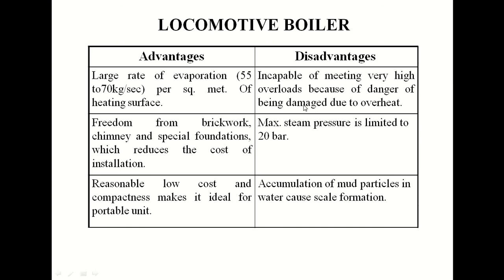And what are the disadvantages? Incapable of meeting very high overloads because of the danger of being damaged due to overheating. Since no firebricks are used, there is a danger of damage due to overheating. Maximum steam pressure is limited to 20 bar, so this is a low pressure boiler. Accumulation of mud particles in water causes scale formation. So this is the main disadvantage of the locomotive boiler.